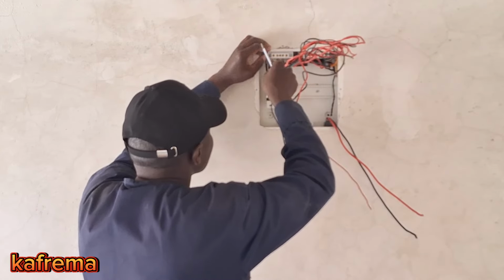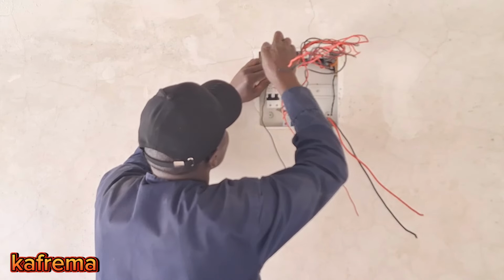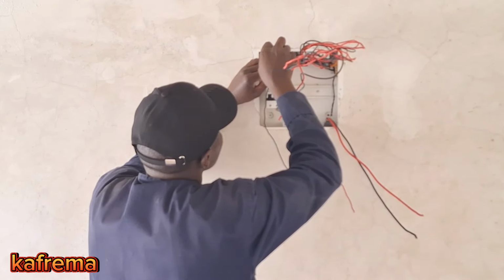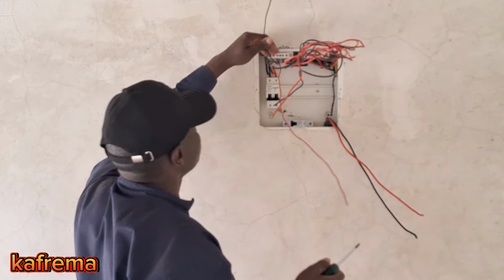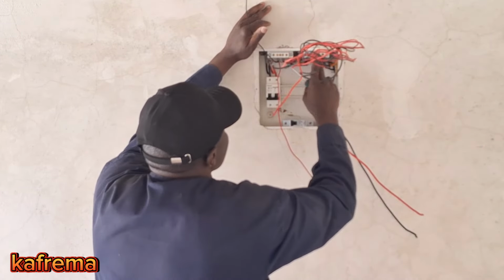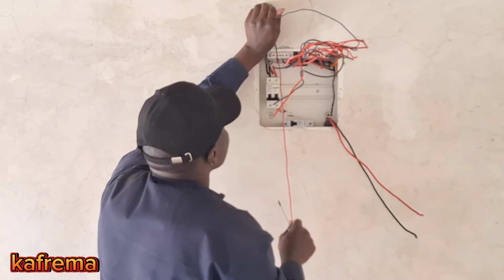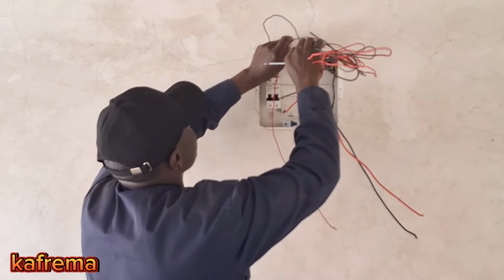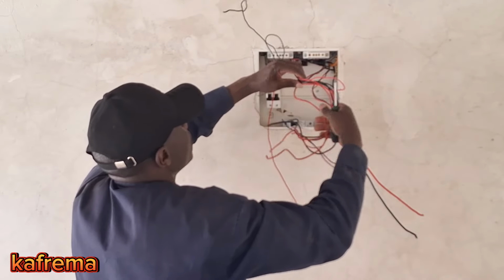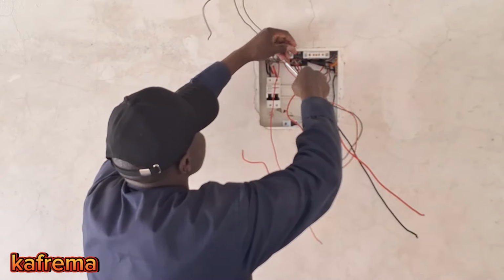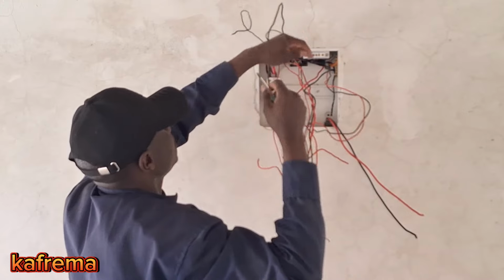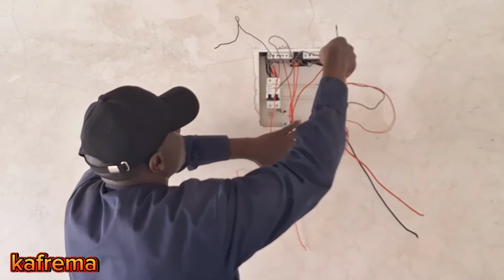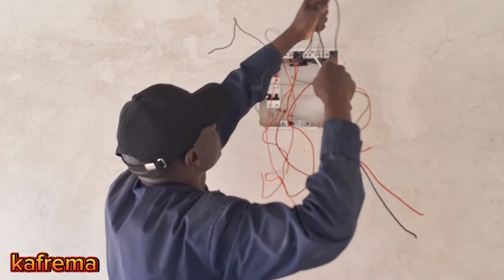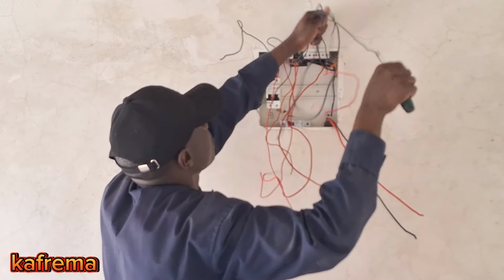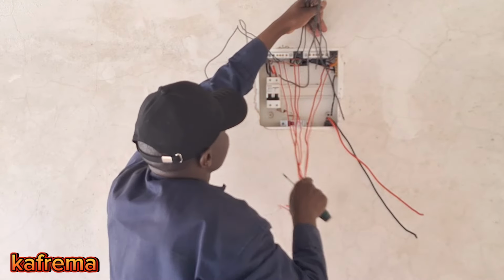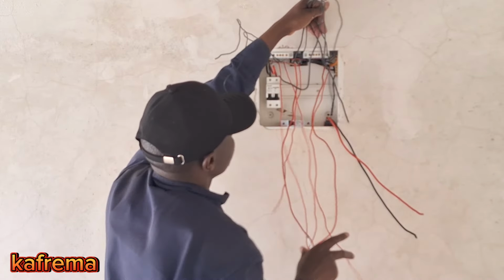First of all, the neutral will go up on this neutral bar. Okay, let me fix all the neutrals on this bar, then continue with the lives. So all the neutral is black. Go according to your color code in your country. Here in East Africa, we use black as our neutral, and red as our live.